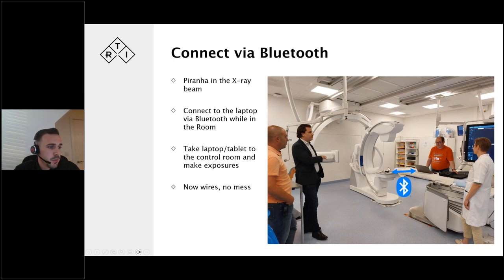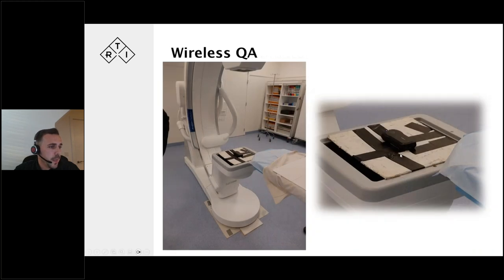So we're in the X-ray room, we place the Piranha and can connect to it in the room to start with, just to make sure we've got the connection. Then we take the laptop to the control room to make the exposures, so we don't need any wires or cables running across the floor or through the doors. We set up the Piranha as seen, ready in the X-ray system.